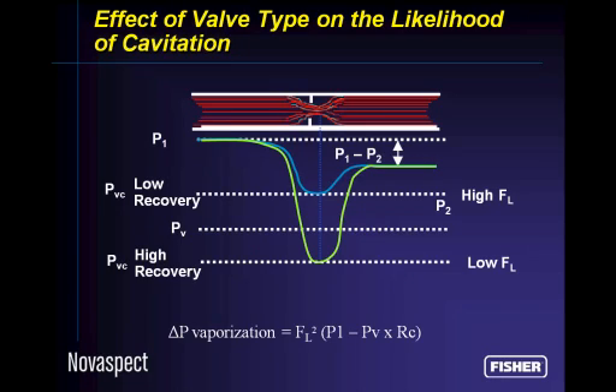What if we could pick a valve that has a bigger or lower dip? You can see the blue valve there. Both valves start at the same inlet pressure. Both valves end up at the same outlet pressure, P2. Okay? It doesn't matter what the valve is that's in there. The inlet pressure and the outlet pressure are the same, as determined by your hydraulic balance, which we discussed. But the point is some valves, which we call low recovery valves, don't dip down so far in pressure inside the valve as a high recovery valve, which dips way down.